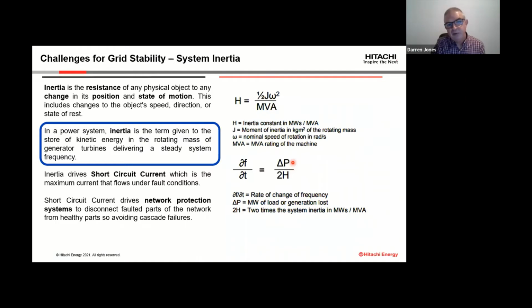Another key part of inertia that we can see here, another way that inertia is used on the system is the amount of inertia drives this change in frequency. Or actually, the more inertia we have, the less of a change in frequency. The change in frequency and the change of time, the rate of change of frequency. The more inertia we have on the system, it simply follows that the more kinetic energy we have, the more fault current that flows. It helps to arrest the change in frequency. As we go back to what we talked about earlier, if we have an imbalance in generation and demand, the more inertia that we have on the system arrests the rate of change of frequency with time.